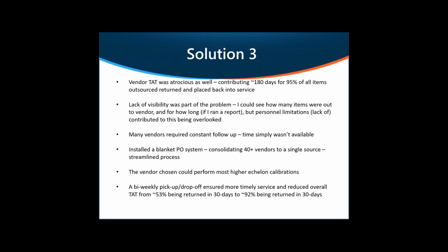Part of the solution was, instead of dealing with all the vendors I had, I found a local source that was able to calibrate most of the things at their facility. I ended up consolidating about 40 vendors into a single source, which could do most of the work locally. We scheduled a bi-weekly pickup and drop-off to ensure the service was constantly being provided for our customers.